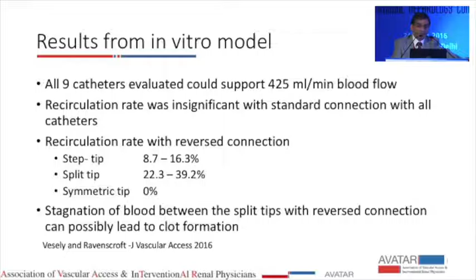Using this model, they evaluated 9 catheters, 3 with step tip design, 4 with split tip design, and 2 with symmetric tip design. Each catheter was tested for recirculation rate, both in the standard and reverse configuration, and for tip movement. So when the catheter was switched from standard configuration to reverse configuration, did that make a difference in how the tip moved inside the right atrium? Did it go closer to the vessel wall or to the atrial wall, making it difficult for the catheter to provide adequate blood flow? Now, these are the problems when we look at just the simulation models.